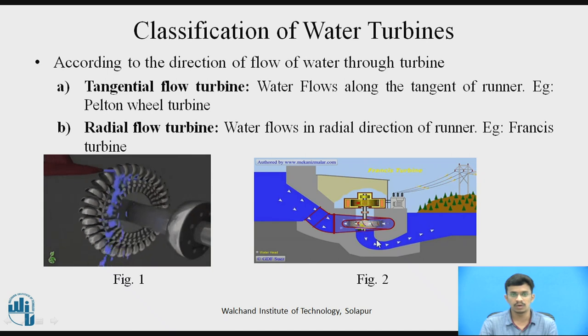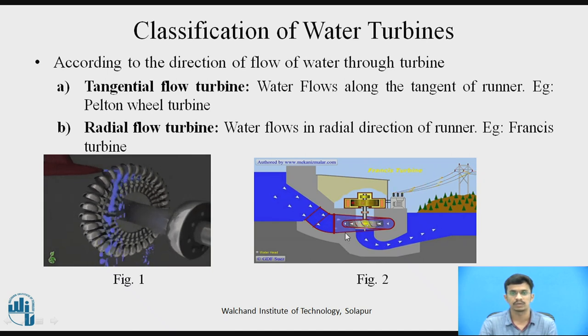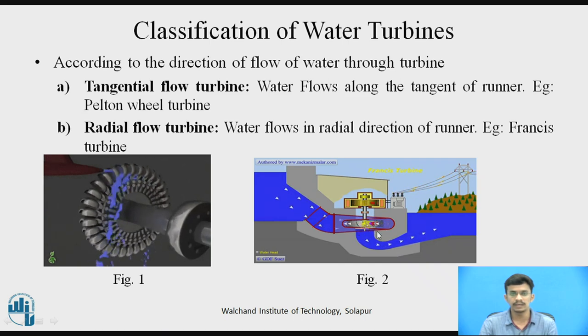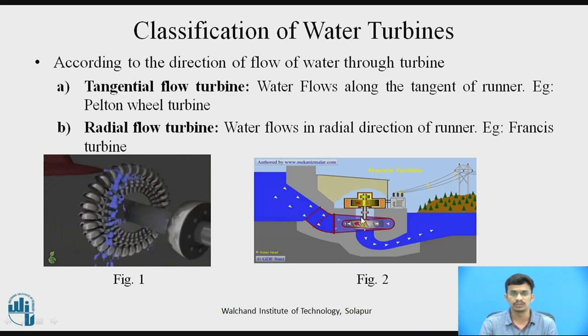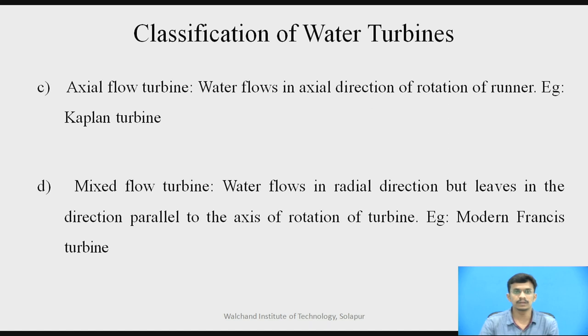In radial flow turbines, water flows in the radial direction of the runner. As shown in figure two, water is applied to the runner in the radial direction to generate electricity. The third type is axial flow turbine, in which water flows in the axial direction of rotation of the runner — the example is the Kaplan turbine. The fourth is the mixed flow turbine, in which water enters in the radial direction but leaves in a direction parallel to the axis of rotation. The example of a mixed flow turbine is the modern Francis turbine.